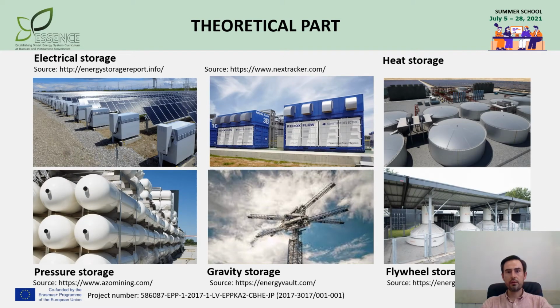Storage devices include all of electrical, pressure, gravitational, flywheel, and heat storage technologies. While the microgrid concept focuses on the power system, heat storage can be relevant to its operation. For example, availability of heat storage will alter the desirable operating schedule of a combined heat and power system, as the electrical and heat loads are decoupled. Similarly, the cooling or heating of buildings will alter the load shape of the heating, ventilation, and air conditioning system, and therefore the requirements faced by electrical supply resources.